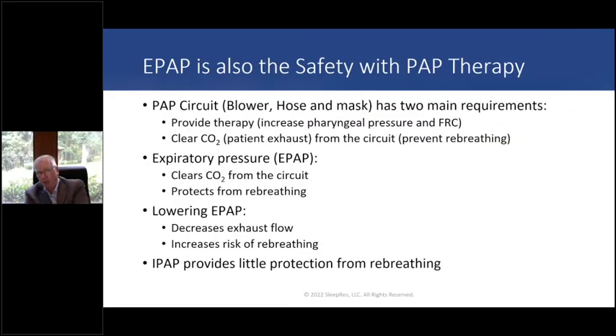EPAP is also the safety part with PAP therapy. The PAP circuit—blower, hose, and mask—has two main objectives. You want to provide therapy, of course, pharyngeal pressure and FRC increase, but you also got to clear the CO2, the patient exhaust, from the circuit. It's got to get out somewhere, through those holes or a mesh vent in the case of a couple masks. You got to get it out of the circuit to prevent rebreathing. If you don't clear it out, the patient's going to breathe it in the next breath. So what does that? Well, it's EPAP. It's EPAP that clears CO2 from the circuit and protects us from rebreathing. If you lower the EPAP, then you decrease the exhaust flow during expiration, and therefore you're going to increase the risk of rebreathing. IPAP provides little protection for rebreathing. So EPAP goes with safety.